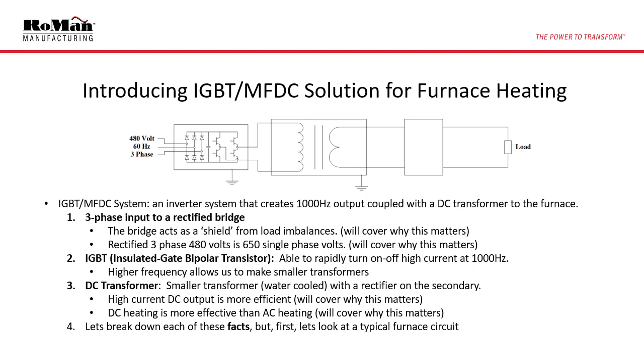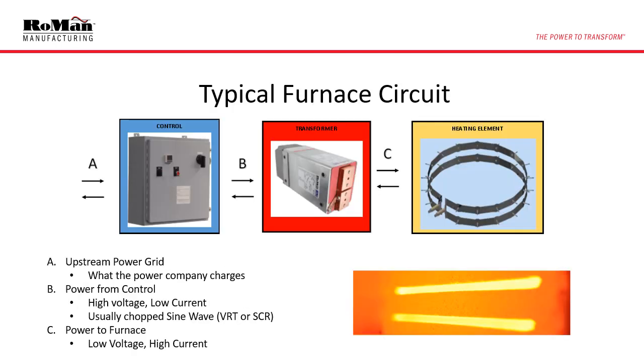To start, let's look at a typical furnace circuit. A typical furnace circuit is comprised of a control, a transformer, and a heating element. As we developed our IGBT MFDC technology, we looked closely at each of these stages of power use. We examined power consumption upstream, i.e. what the power company sees. We measured the power between the control and the transformer, which is usually high voltage, low current. And then we looked at the power between the transformer and the heating element, typically low voltage, high current. In order to understand our value proposition, I want to go into detail about the cost and loss of power at each of these steps.